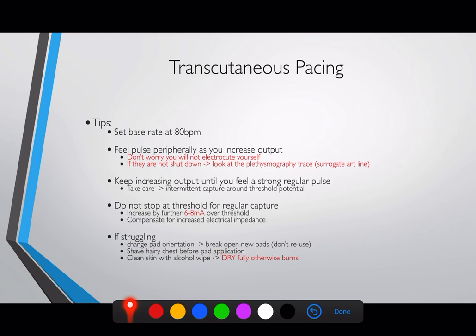If you shave them, make sure you dry the skin. Very occasionally the electric coupling is not great — often with patients who use a lot of body moisturiser. Clean the skin with alcohol wipes to remove oils, but make sure the alcohol is completely dried. I tend to take a saline swab to wipe everything down, then dry gauze, then stick the pads on. Any alcohol remaining can potentially cause burns.